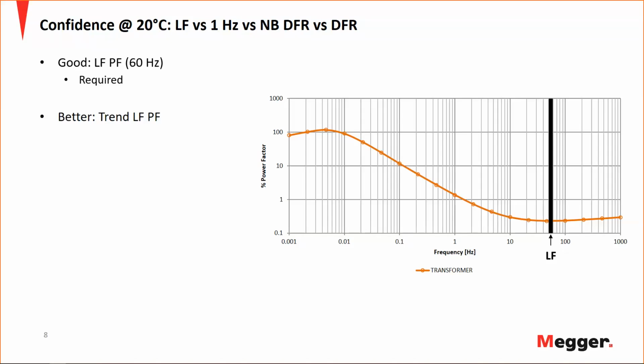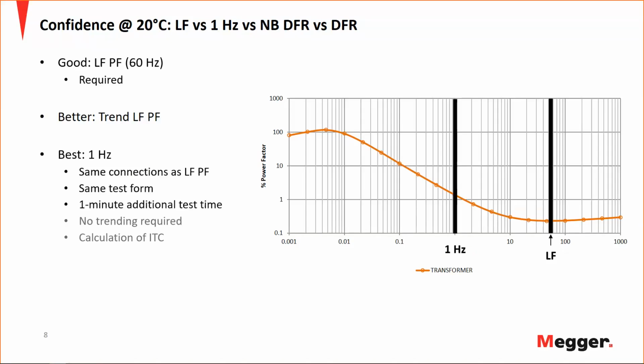To get better confidence, you can trend line frequency power factor over time. But again, I would challenge those in attendance to say that they have good power factor measurement history. They could always trend everything. It's not necessarily the case. So what you can do, the best thing that you can do is use a piece of power factor test equipment that can test at 10 kV line frequency and also test at 1 Hertz, using those same connections, using the same test form, and only adding 1 minute of additional test time. And most importantly, it gives you an immediate assessment of your insulation without the need for trending.